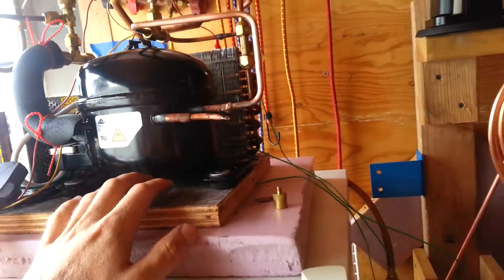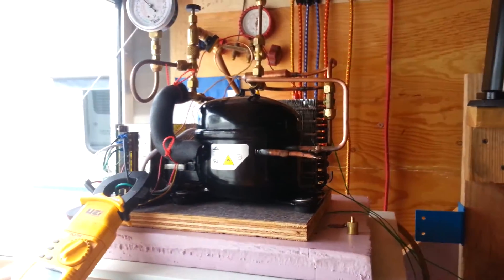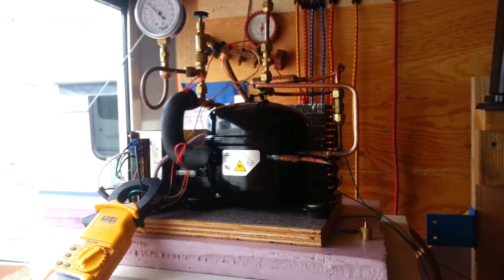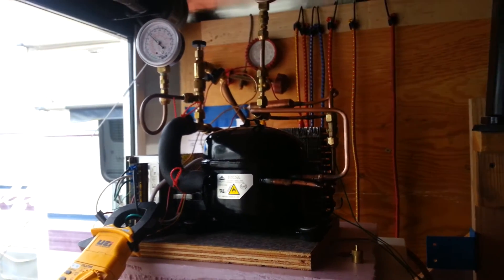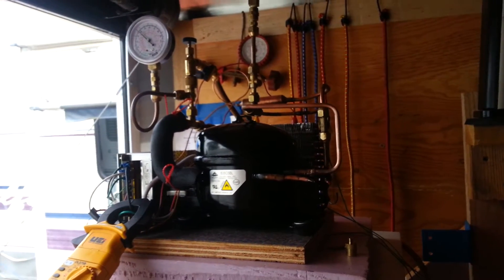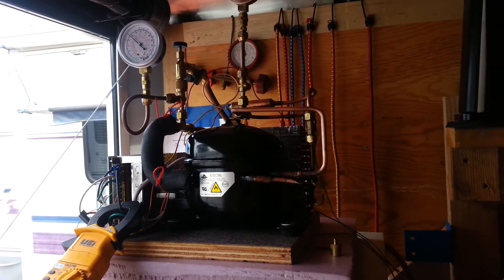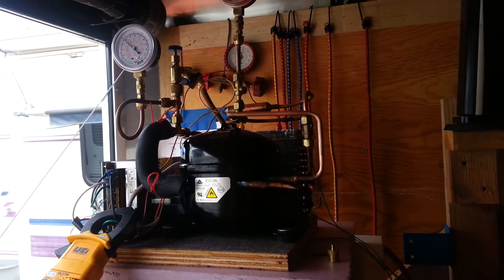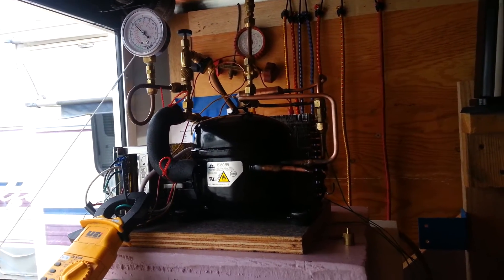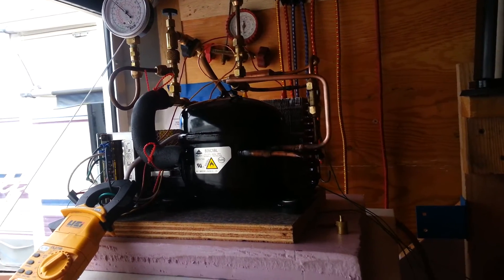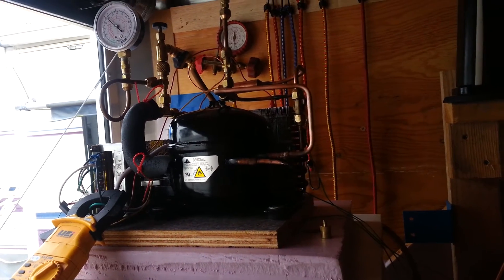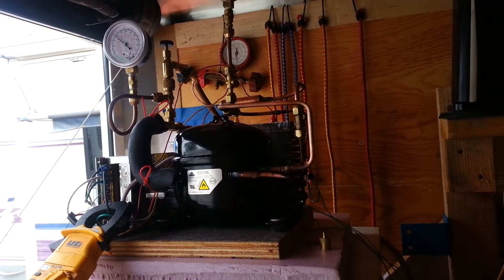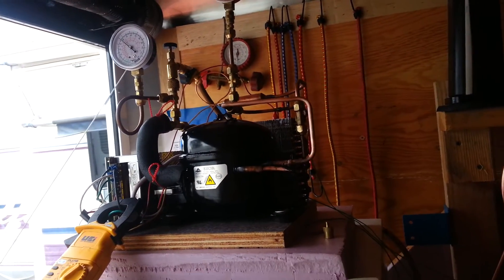So I ran it a bit this morning. I maintained the same cap tube. It's four feet of 031. Didn't really know if there was going to be much difference. I assumed there was going to be a difference, but the best thing to do is just to swap out the compressor and observe the operation and then adjust it accordingly. Right now, it seems to be working pretty well.